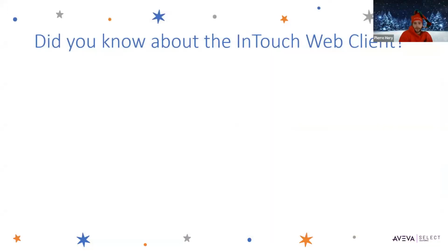Yep. So just a quick summary. The main difference between InTouch Web Client and InTouch Access Anywhere, although they both can give you remote access to your InTouch applications with read and write capabilities, is that InTouch Access Anywhere is an RDS-based approach using remote desktop services, while the InTouch Web Client is a browser-based approach.